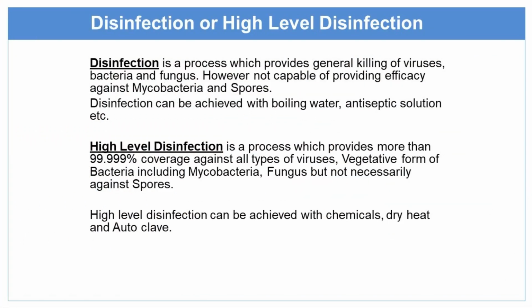Disinfection or high-level disinfection. Disinfection is a process which provides general killing of viruses, bacteria and fungi, however it is not capable of providing efficacy against mycobacterium and spores. Disinfection can be achieved with boiling water, antiseptic solution, and then high-level disinfection. High-level disinfection is a process which provides more than 99.9% coverage against all types of viruses, vegetative forms of bacteria, including mycobacteria, and fungi, but not necessarily against spores. High-level disinfection can be achieved with chemicals, dry heat and autoclave.